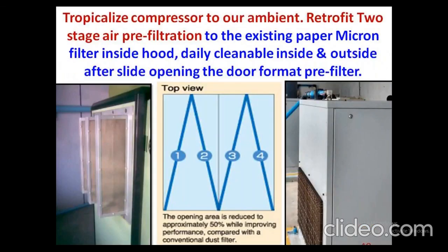Coming to the air intake for the given compressors, we are in India. A tropicalized climate has so much SPM, suspended particulate matter. And in a textile mill there is more hairiness and more fluff. You are supposed to have a two-stage pre-filter. One is a Netlon type SS mesh with a 30 degree angle. This needs to be fixed on all the textile mill screw air compressors. Then you go for a polyurethane filter. This is washable, cleanable, daily washable and daily cleanable.